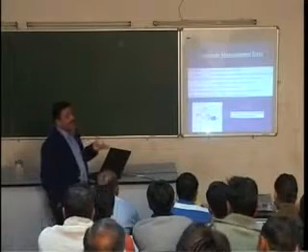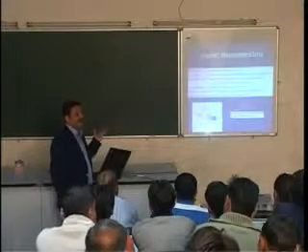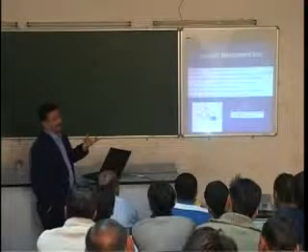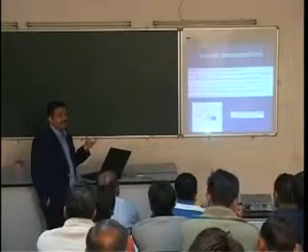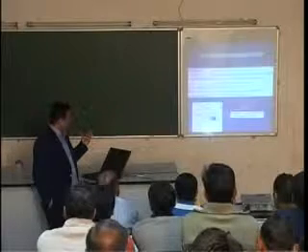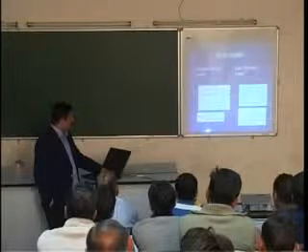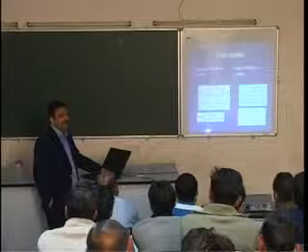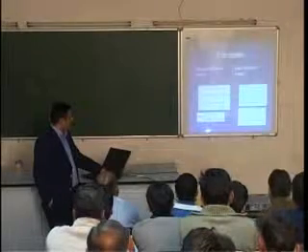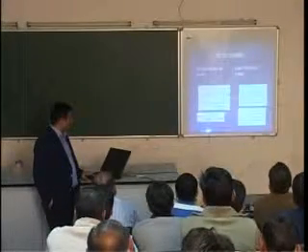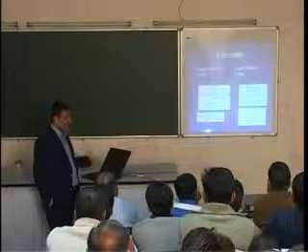So there are nearly 12 terms which have to be corrected before you start the measurement of any device, even for a simple reflection coefficient measurement or transmission loss measurement. You have to remove those 12 errors, even for that sophisticated device called a VNA. Only then can one ensure that the measurement you are carrying out is what you require. So this is the model of your two-port VNA, and you have to remove each error, and then once you remove the error, your S11M, which is measured, and S11, which is actually that of the device, will be the same.